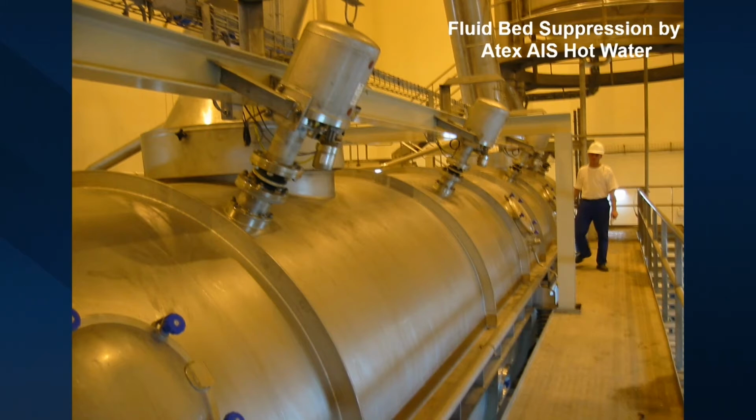At the same time, we premix the fuel that could be ignited with this powder, and then it cannot be ignited anymore, and therefore we quite often also call it an advanced inerting system. That means we mix sodium bicarbonate powder with the fuel, and then it cannot explode anymore.